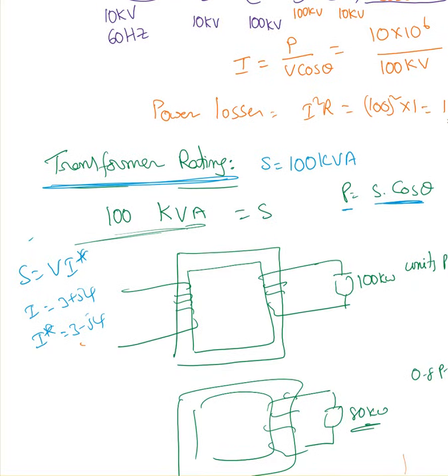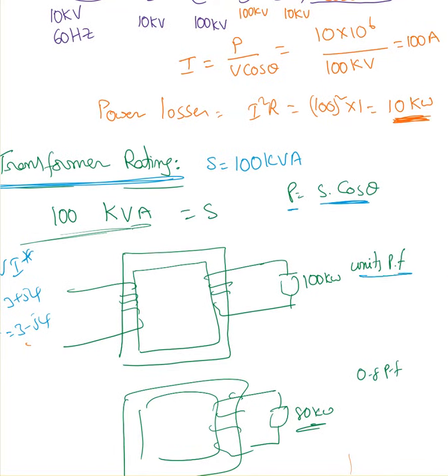For example, if your power factor is unity, then a 100 kVA transformer will produce 100 kilowatts of active power. If your power factor is only 0.8, it will produce only 80 kilowatts of active power. That is the reason the transformer is always rated in kVA.